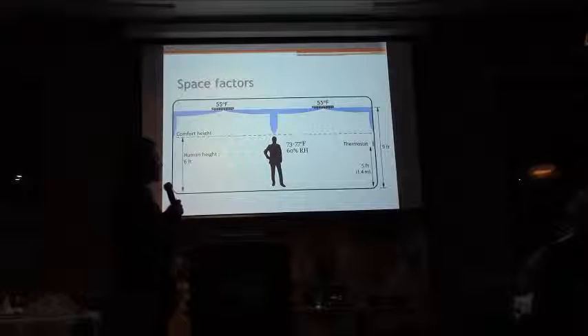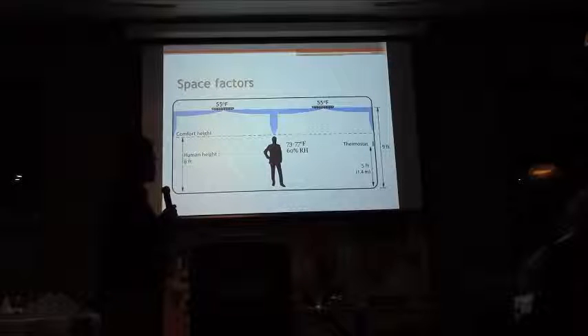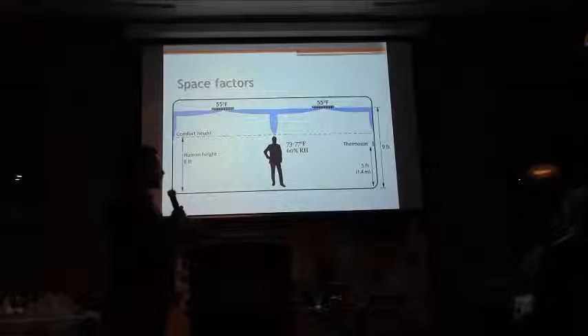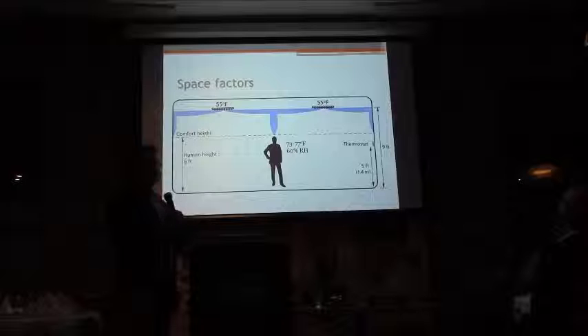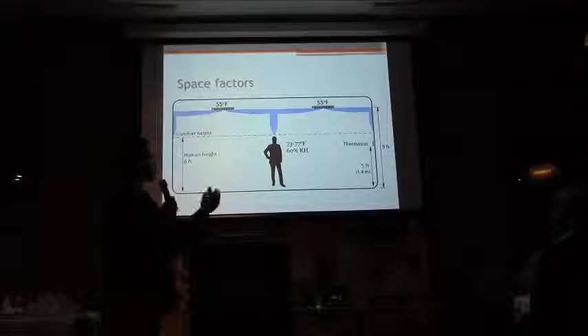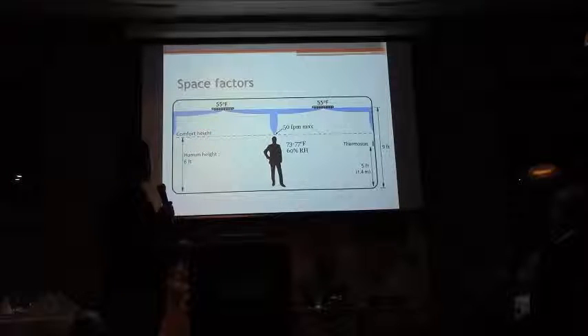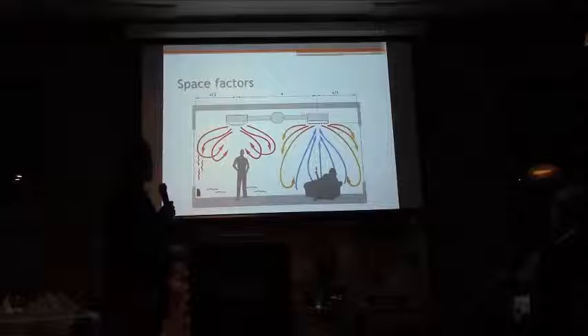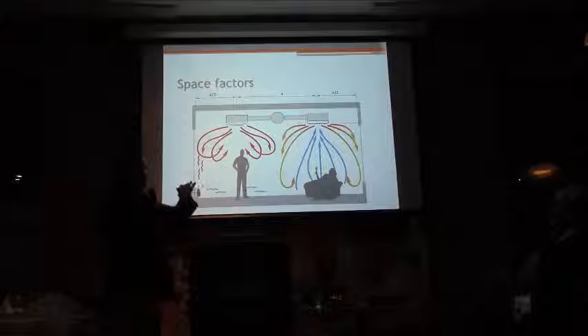You want to have a maximum relative humidity of 60%, minimum 30%. The minimum humidity is not defined by ASHRAE, but anything lower than 30 is just too dry, so try to always stay between 30 and 60. So maximum velocity of 50 feet, I said that. You want to avoid hot air stratification at all time.